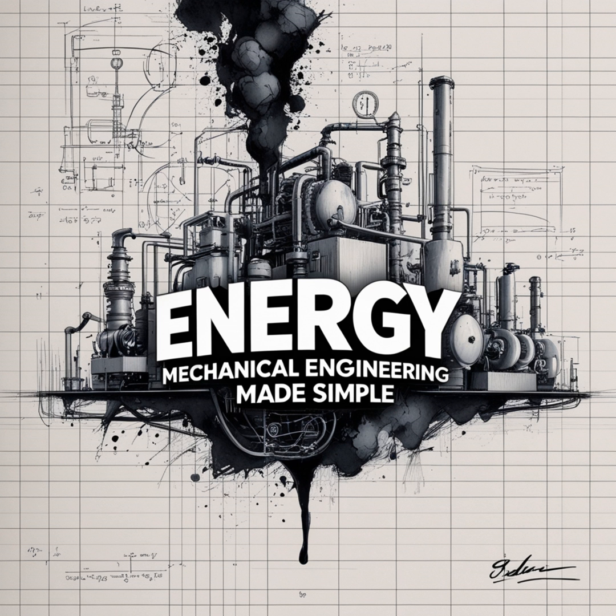So the machine's performance curve shifts down to meet the system curve at the lower required flow rate, naturally. Precisely. And because of that N-cubed relationship for power, the energy savings are enormous. We're talking millions of kilowatt hours per year in large industrial or HVAC systems. It's a major factor in energy conservation.